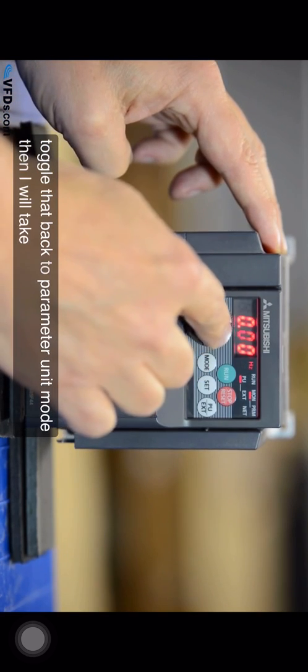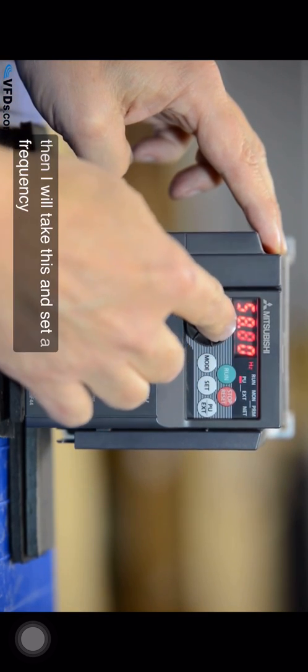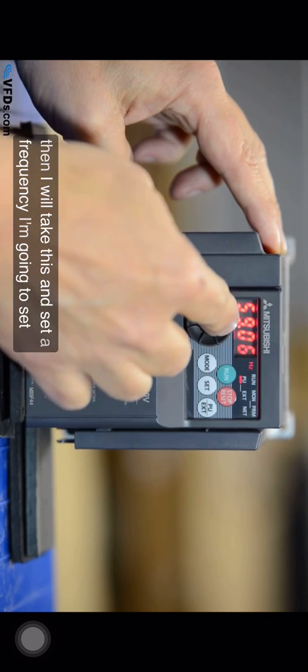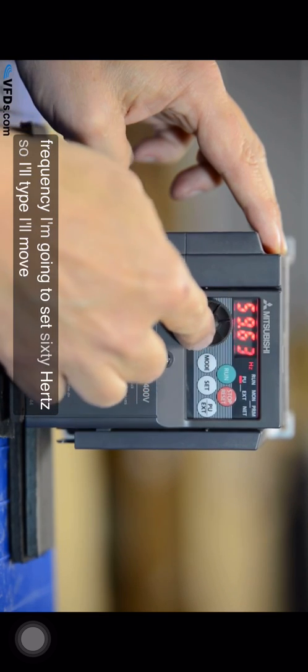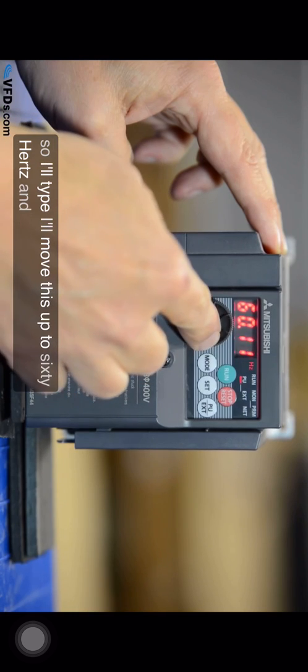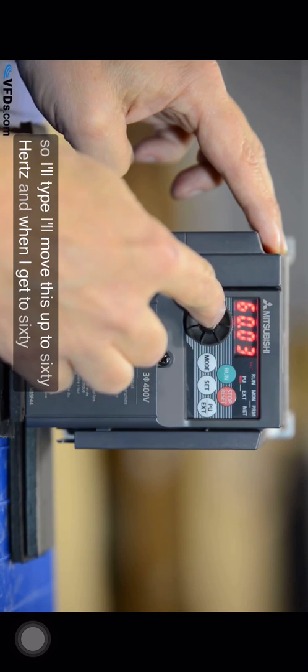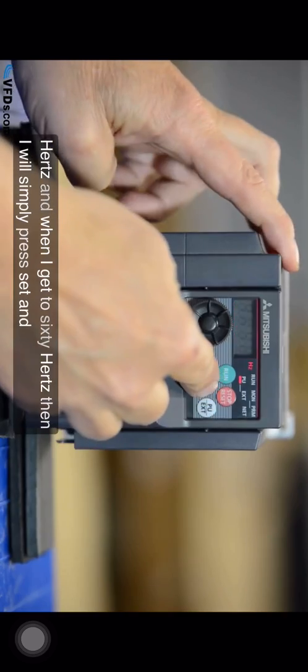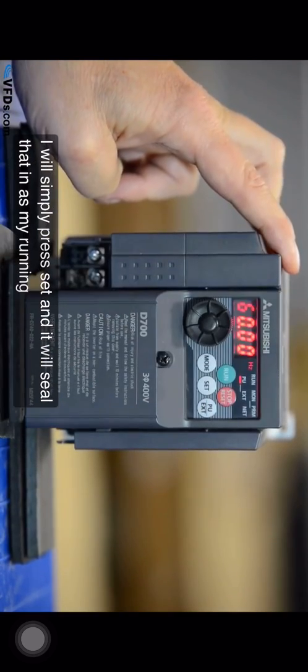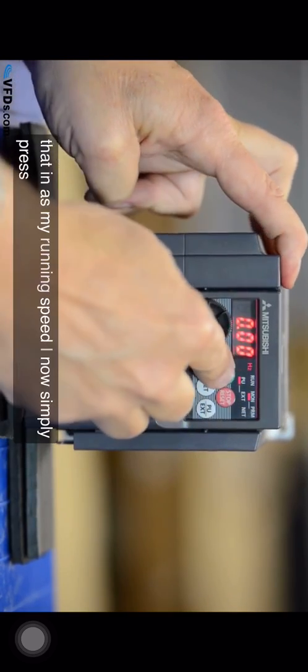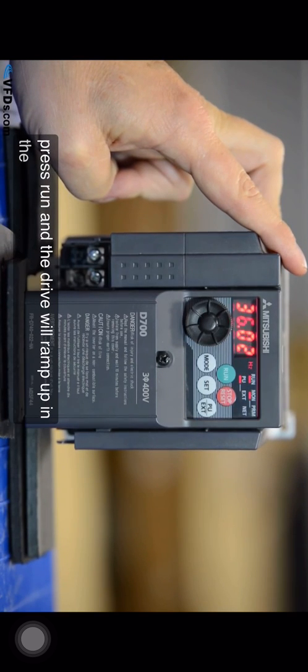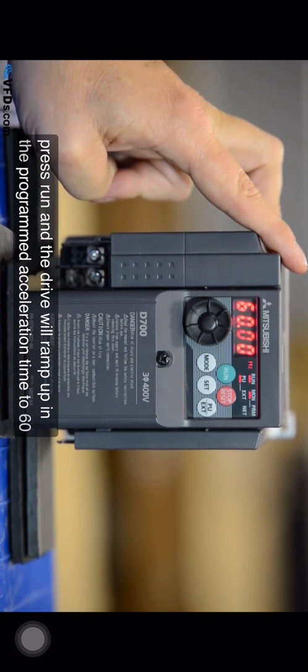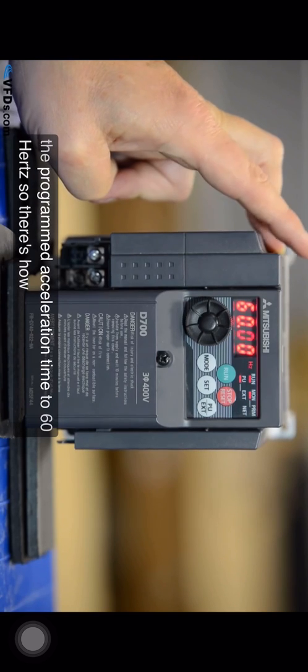Then I will take this and set a frequency. I'm going to set 60 hertz. So I'll move this up to 60 hertz and when I get to 60 hertz then I will simply press set and it will seal that in as my running speed. I now simply press run and the drive will ramp up in the programmed acceleration time to 60 hertz. So there's how you run.